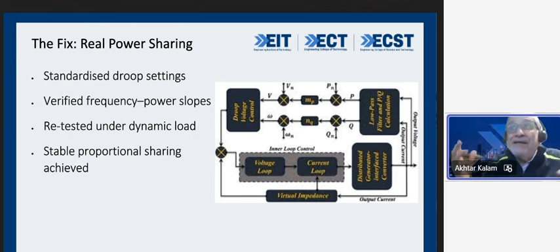So now we know the problem, we know the root cause. How do we fix it? We still need to run the two machines in parallel, isn't it? We want them both to share the load - that 100 megawatt, I want one of them sharing 50 megawatt, the other sharing 50 megawatt, if you want a perfect world. The first thing I would do is standardize my droop setting. If one was 4%, the other should have been 4% also. Then look at the frequency power slopes, retest under dynamic load, and do a stable proportional sharing till that is achieved. So once the droops were matched, the problem disappears. Immediately, no more problem. It started sharing.